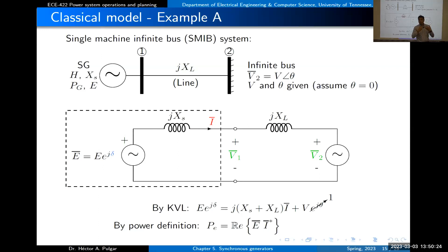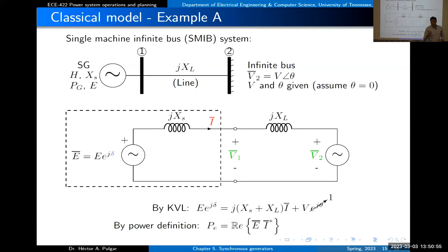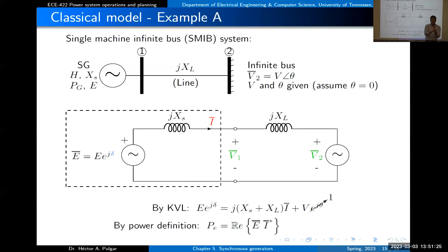Delta is also called the rotor angle or loading angle. It's the angle that separates the flux generated in the rotor from the flux induced in the stator windings. The more power that needs to be transferred, the larger the torque applied, making that angle larger. The maximum angle for a cylindrical rotor with no losses is 90 degrees. The loading angle describes how much the machine deviates from the nominal position, which corresponds to running at constant nominal speed.